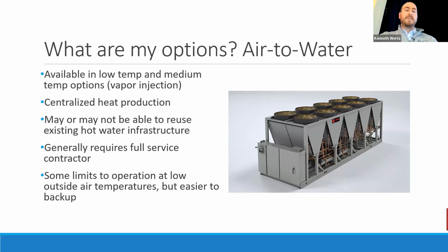So it makes it an inherently more expensive project, unfortunately. And we'll talk again that these units can operate down to low temperatures, but not all the way down. So often you have to have a natural gas backup, which is both good and bad in certain ways.